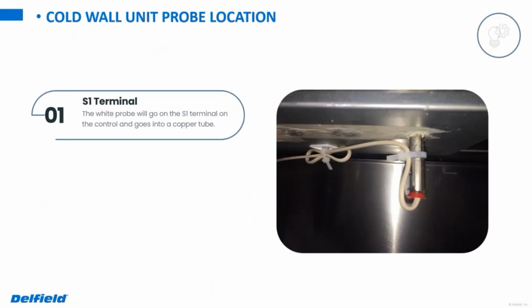All right. Moving on from there, if you have a unit that has a cold wall, usually a unit with a reach-in cooler on the bottom and then a cold rail on top, we're typically going to have a white probe for those. It'll usually just go into either a stainless steel or a copper chase, and then that plugs into the S1 terminal on that control. So it'll be a de facto air sensor on those as well.